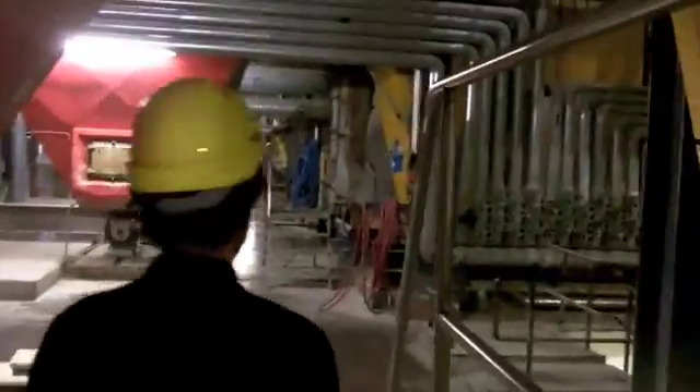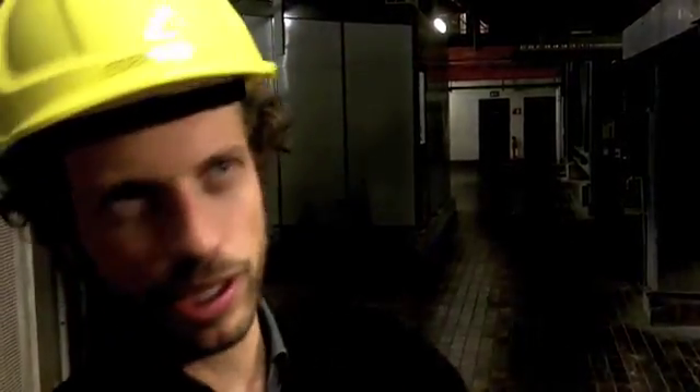In the center of the building where we have the ovens — you can actually hear them. You can hear the waste being thrown around inside the ovens. This one inside here is 950 degrees Celsius. You can put your hand on it. The heat is coming from the ovens and going over to these boilers where they boil off water using the hot heat. The product is steam coming up to 400 degrees Celsius, and that is drawn further on into the turbine to make district heating and electricity.